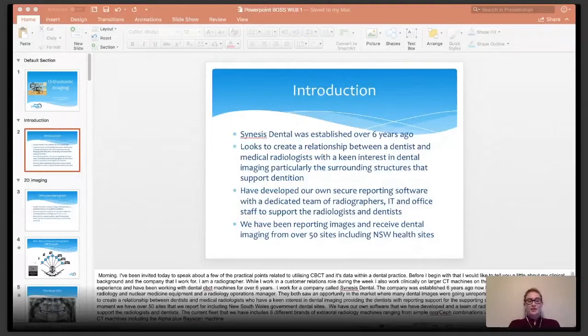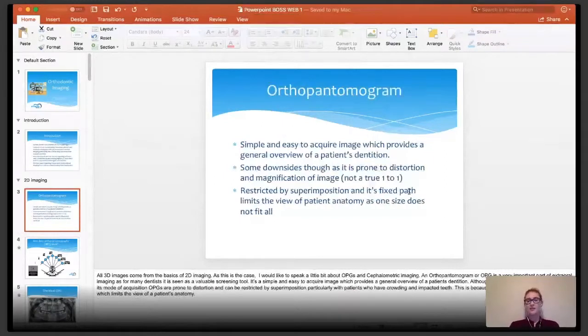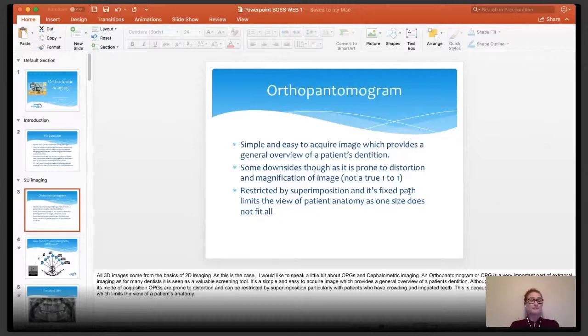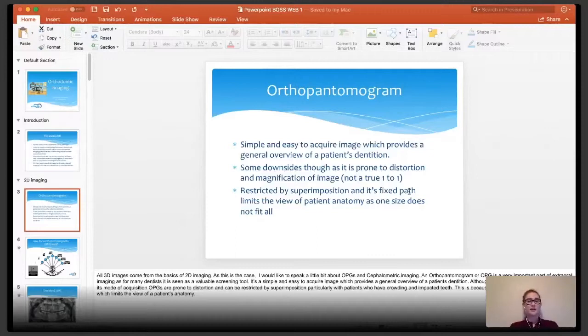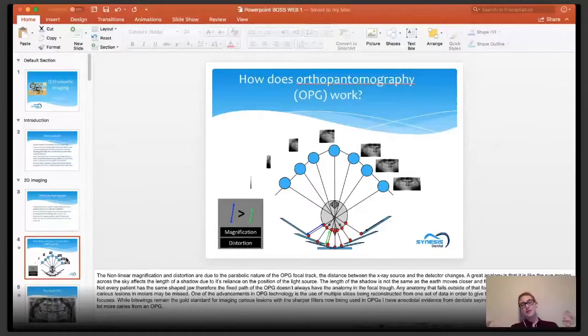I'll move on to our 2D imaging now. With OPGs, this is your basic imaging, providing you with an overview of all images of your patient's general dentition. It's a simple and really easy to acquire image which provides that general overview. It does have downsides though — it is prone to distortion. It is not a true one-to-one image; it can be magnified due to the distance between the source and the detector changing as it spins around the patient's head.